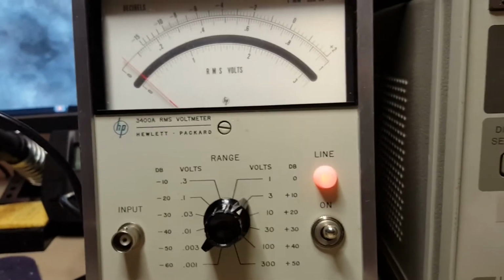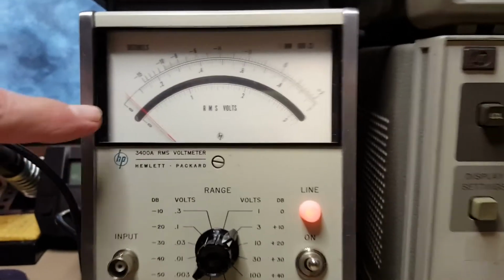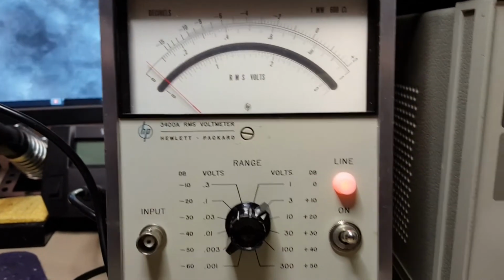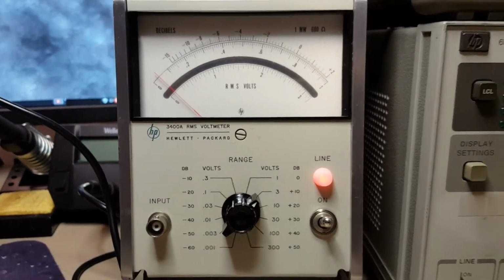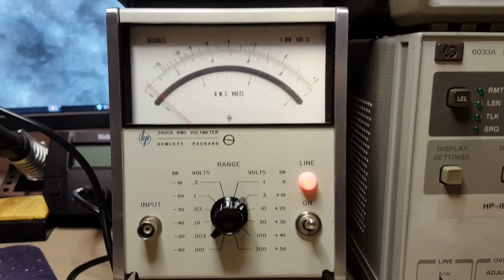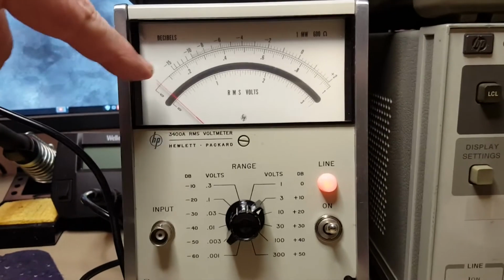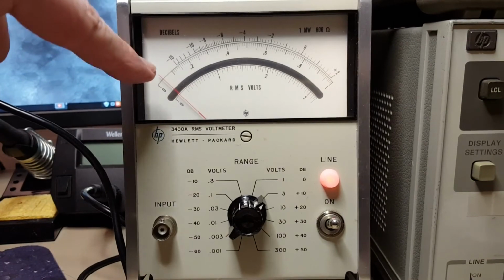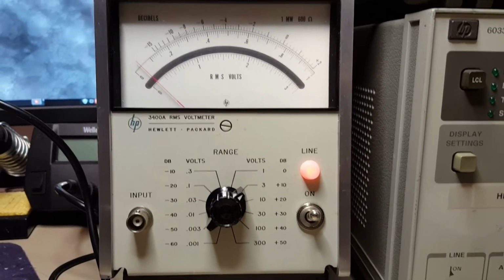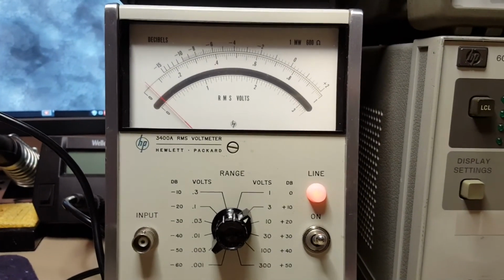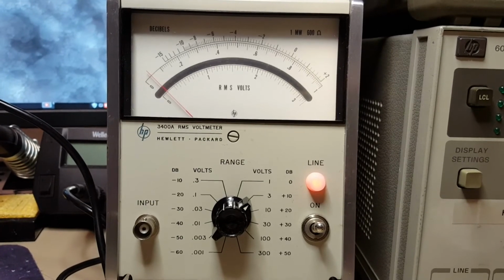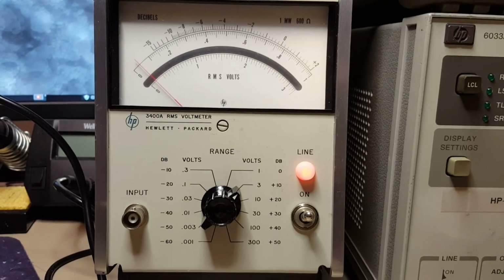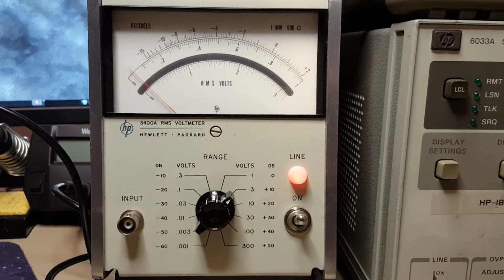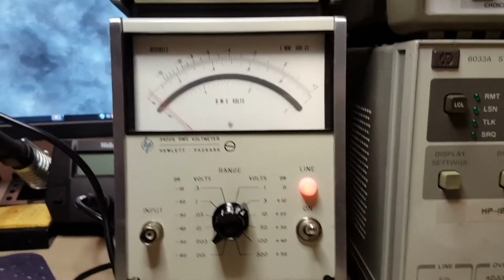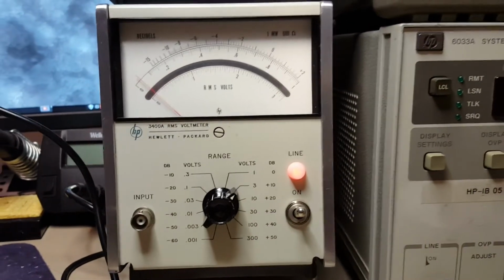The other thing I wanted to point out is that this particular meter always has a little bit of offset. This is by design. This is talked about in the service manual. This is why the bottom 10% of this meter is not graduated. And like I said, it's just the way the meter works. It's normal. Even the 3400B, which is the very latest model, still has this area that's ungraduated.